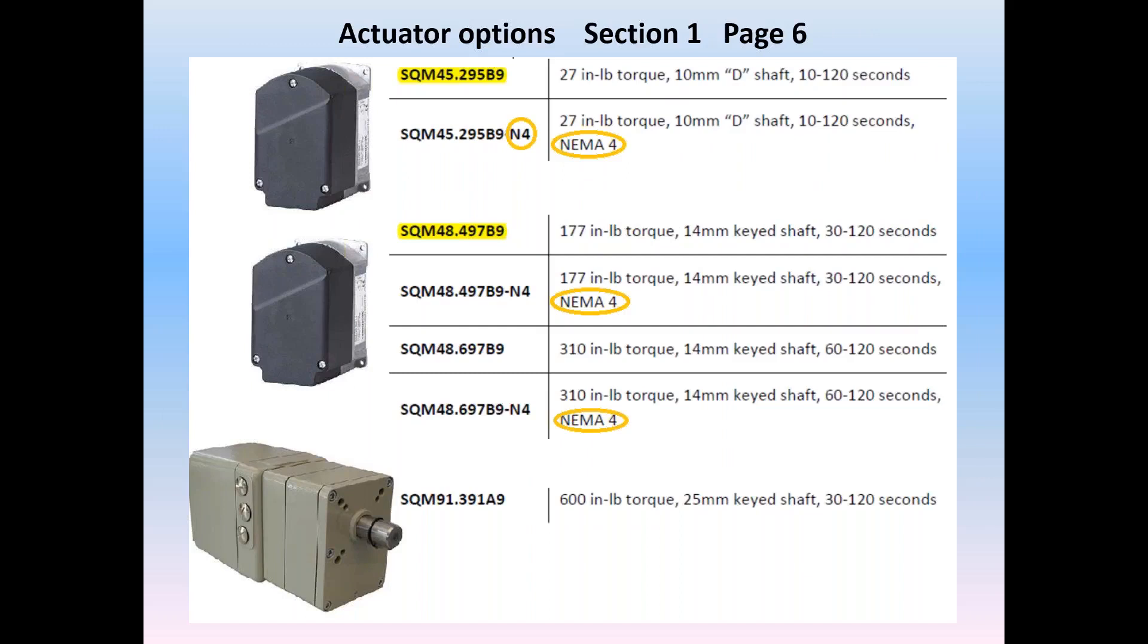The LMV5 is the brain of the system. While the LMV5 is the brain of the system, the actuators are the muscle. Four torque ranges are featured and shown here, and the SQM5 units can be ordered with NEMA 4 kits. The SQM9 is NEMA 4 with no additional shaft seal required. As the torque values increase, so do the minimum running times. All units will operate at the same speed dictated by the LMV5's program settings, up to 120 second ramp times.